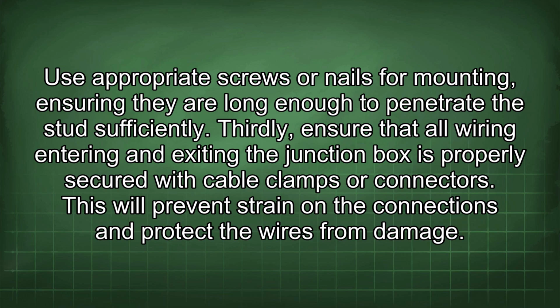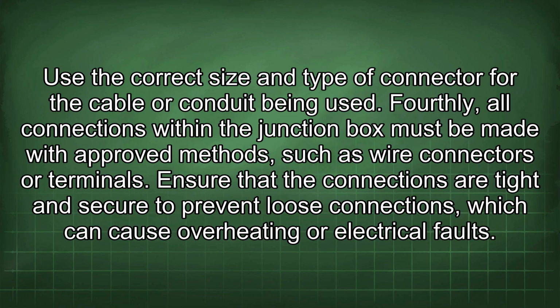Thirdly, ensure that all wiring entering and exiting the junction box is properly secured with cable clamps or connectors. This will prevent strain on the connections and protect the wires from damage. Use the correct size and type of connector for the cable or conduit being used.